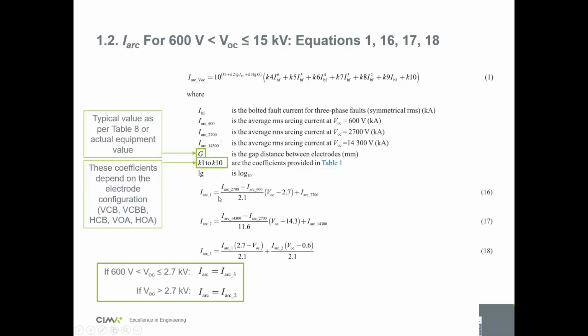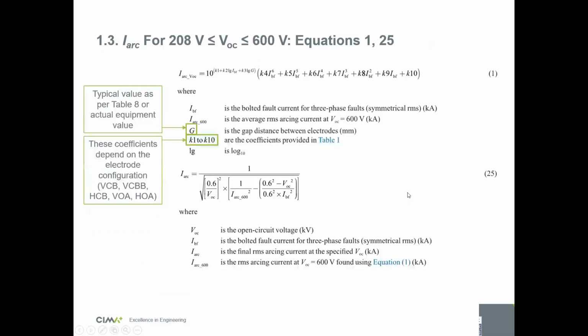You need to calculate IARC 1, IARC 2, and IARC 3, and then your final IARC: if you're between 600 and 2.7 kV, it's IARC 3. If you're above 2.7 kV, it's IARC 2. So you see, to find the IARC, it's at least 6 equations instead of 1. Now, if your voltage is below or equal to 600 volts, it's much simpler. It's only 2 formulas. You have the IARC 600 to calculate with a bunch of factors, and then you find your IARC final with this small equation here. Even if it's simpler, below 600 volts it's still more complex than the 2002 version.